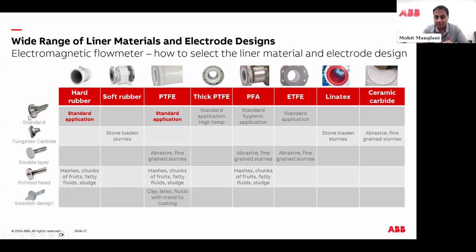In terms of electrode designs, 99% of the time, standard electrodes work just fine. Tungsten carbide is used primarily with the ceramic liner, where it has substantial hardness. You have double layer for extra protection. You have a pointed head for applications with rags or pulp, where it will cut through the process if something is coating a standard electrode. And then we have our famous Swedish design shark fin electrode. Compared to the pointed head, the Swedish design is a bit more expensive and limited in terms of available materials, but essentially you can cut up your process even better.